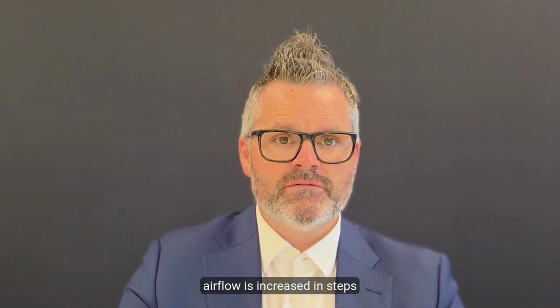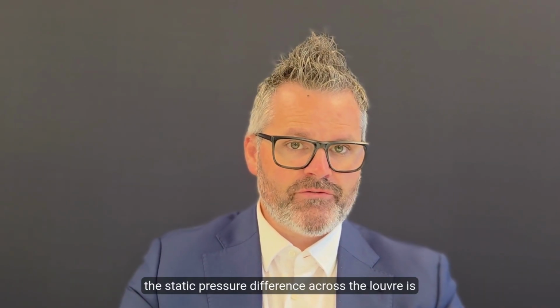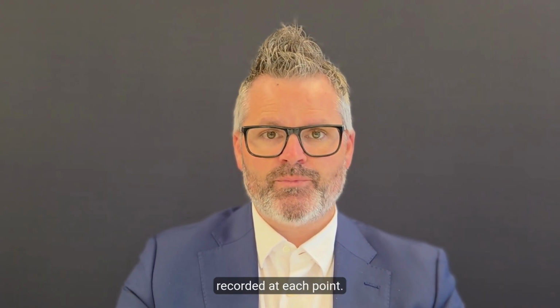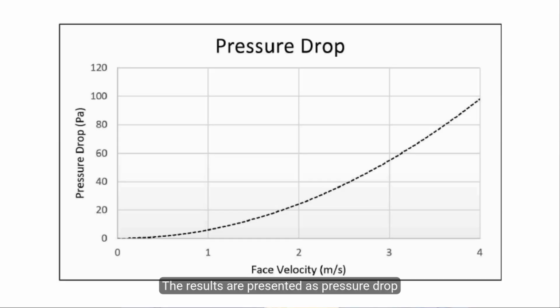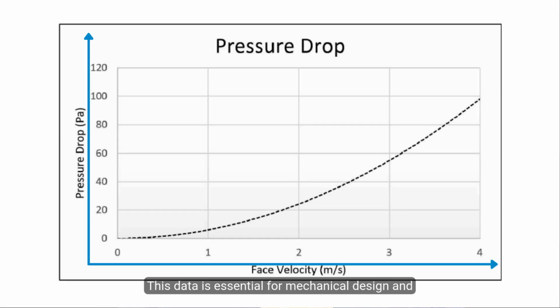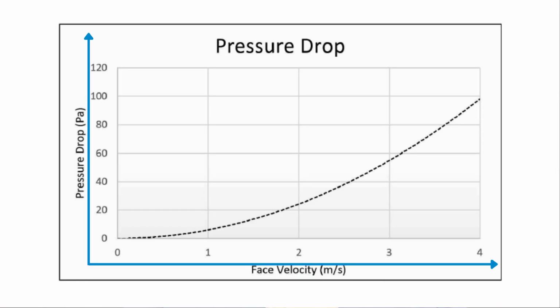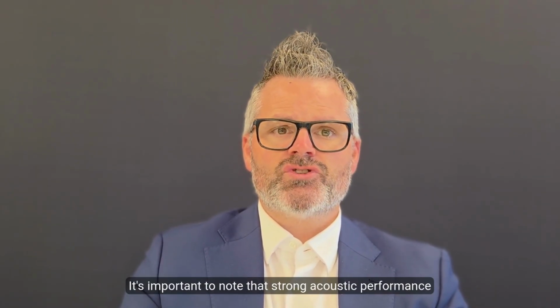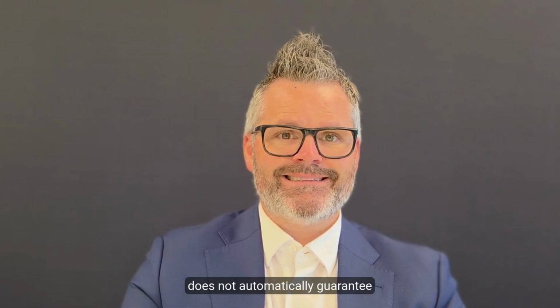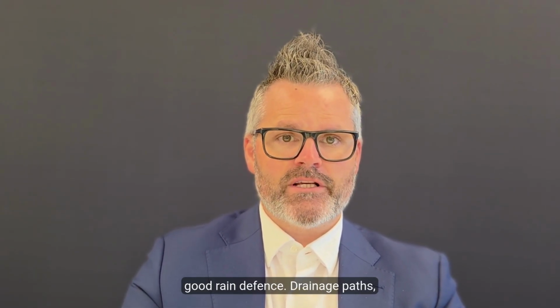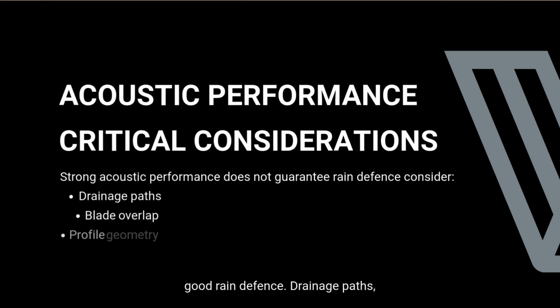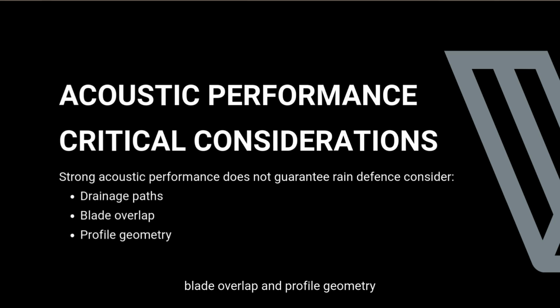For pressure loss, airflow is increased in steps, and the static pressure difference across the louver is recorded at each point. The results are presented as pressure drop curve versus face velocity. This data is essential for mechanical design and fan selection. It's important to note that strong acoustic performance does not automatically guarantee good rain defence. Drainage paths, blade overlap, and profile geometry remain critical.